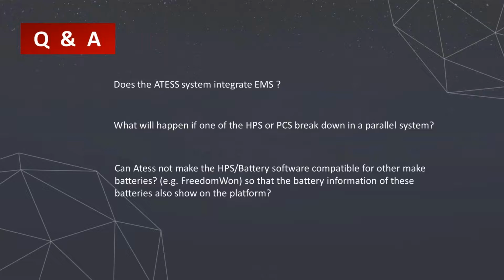Question 1: Does the ATESS system integrate EMS from a third party? Actually, our HPS and PCS have built-in control systems, which we can call EMS in a narrow sense. This basically meets the control logic requested by most customers, so most of the time customers don't need to configure an EMS system separately. Of course, our equipment can also comply with EMS from a third party. In that case, we provide our Modbus protocol to the third-party EMS and accept instructions from it through RS485 communication.